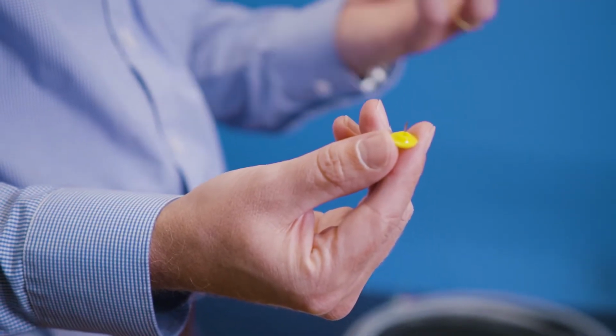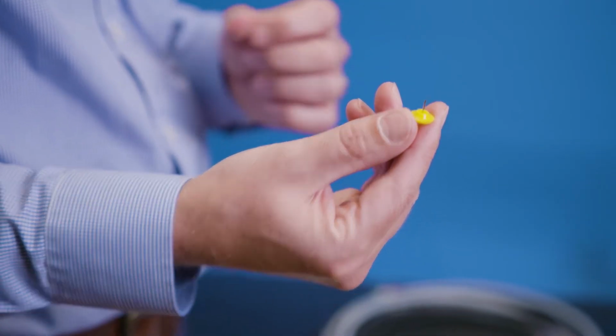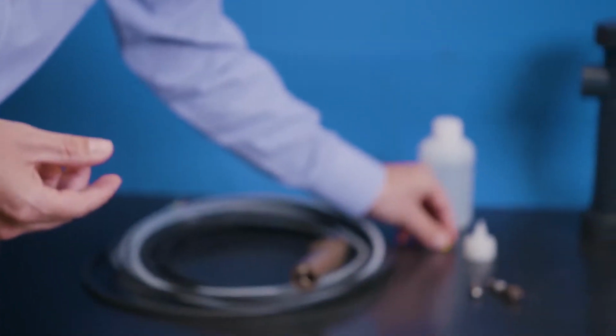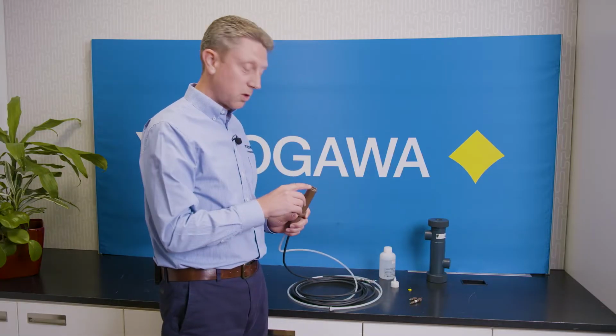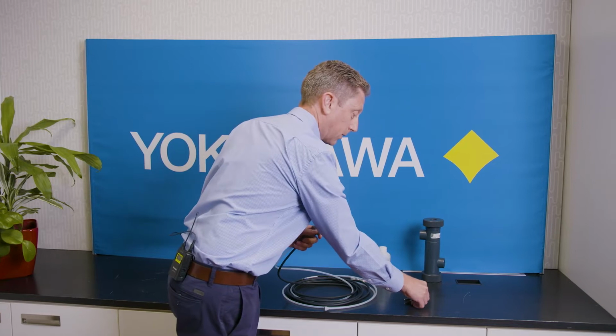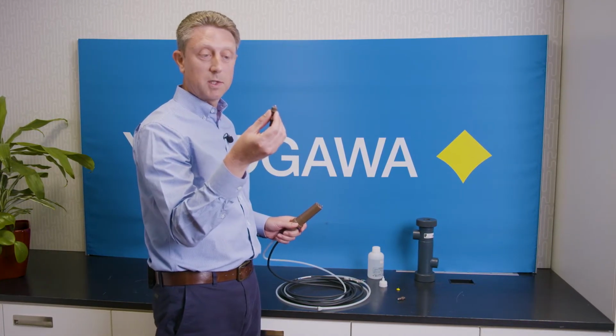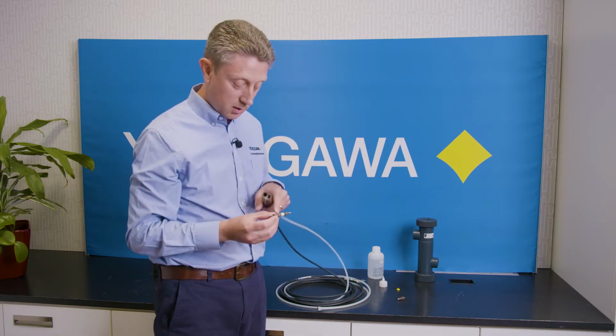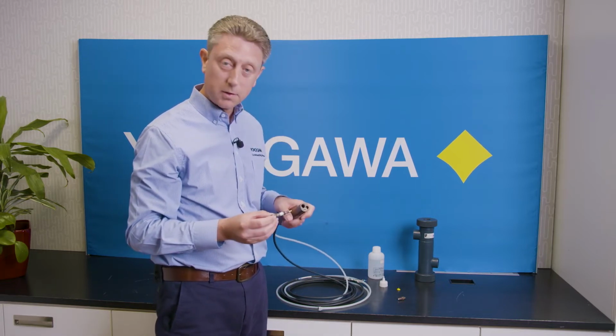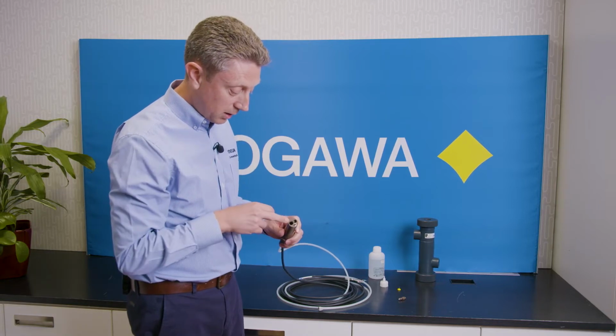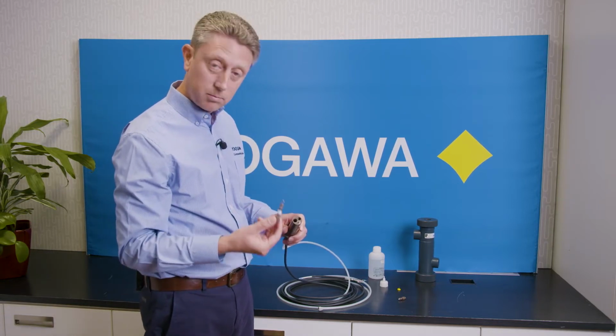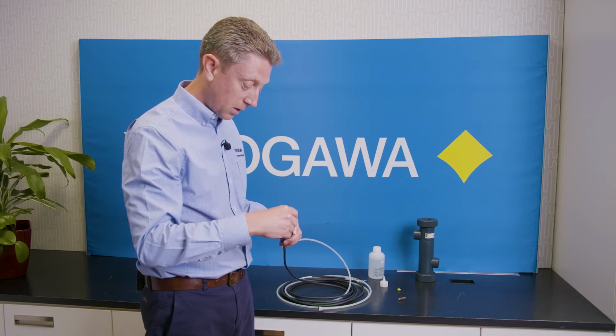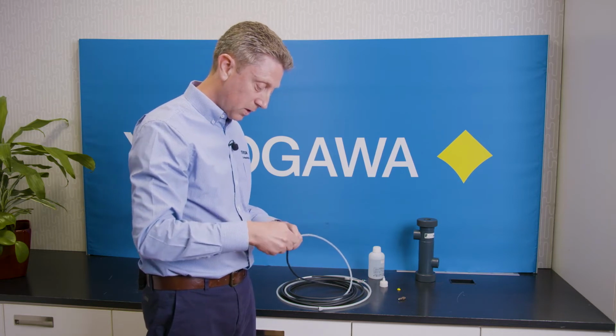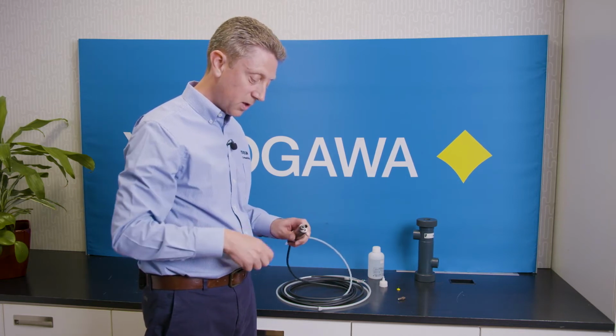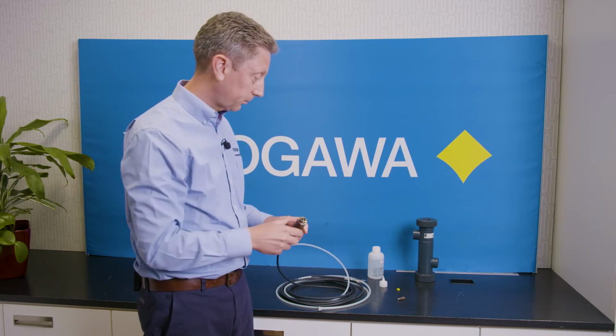So we can have a look now at how we actually assemble this sensor. So the first thing we need to do is screw in our pH glass electrode. So we can have a quick assessment and double check there's no obvious damage to the glass, and also check that the O-rings are in place on this sensor. When you look at the end of the probe, it should become obvious which hole the glass screws into. So we can screw that in and just nip it up finger tight and make sure the O-rings are sealed.